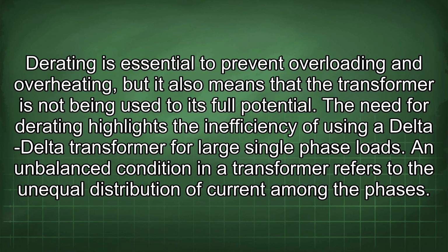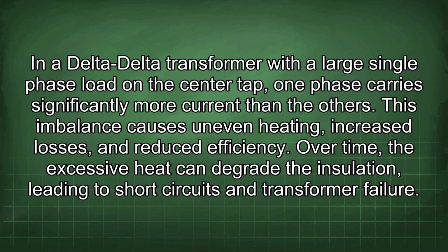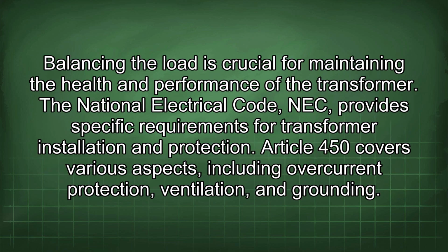An unbalanced condition in a transformer refers to the unequal distribution of current among the phases. In a delta-delta transformer with a large single-phase load in the center tap, one phase carries significantly more current than the others. This imbalance causes uneven heating, increased losses, and reduced efficiency. Over time, the excessive heat can degrade the insulation, leading to short circuits and transformer failure. Balancing the load is crucial for maintaining the health and performance of the transformer.